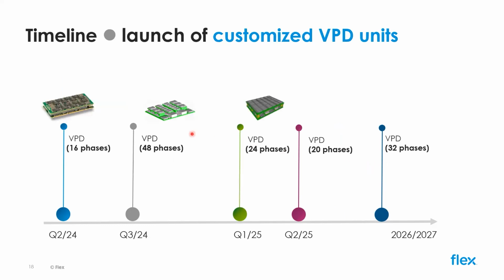Finally, in terms of the next products coming through, we've talked about vertical power delivery on a general level. You'll see in this slide there are no part numbers listed, and the reason is that each and every one of these is a custom development. We're working closely with key customers in these areas, those that demand the benefits of vertical power delivery — mounting the module directly underneath the processor, improving the power distribution networks by reducing resistance, inductance, etc., and also improving the transient performance of the modules, as well as freeing up space on the top of the board.